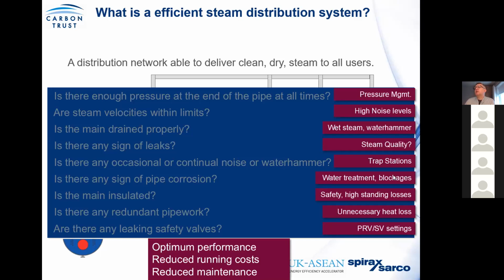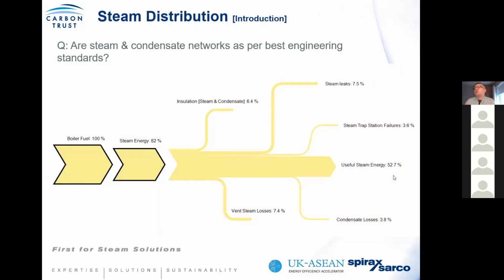Now, let's start looking at potential areas. So again, we start looking at what the International Energy Agency says, and then we start looking at where the losses are attributed to the system. So we could find that on average, about 6% of your fuel energy is lost through distribution. There are multiple case examples where you would see exposed valves. Simple things like this are quite a significant energy loss, acting as large radiators. So they can easily be addressed by improved efficiency or insulation jackets around valves, for example. So you'll also find steam leaks, for example.